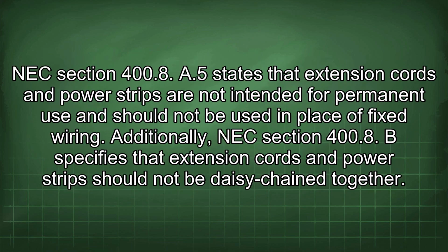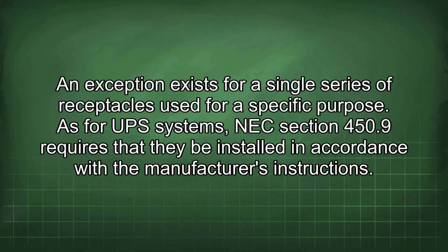NEC Section 400.8 A5 states that extension cords and power strips are not intended for permanent use and should not be used in place of fixed wiring. Additionally, NEC Section 400.8 B specifies that extension cords and power strips should not be daisy-chained together. An exception exists for a single series of receptacles used for a specific purpose.